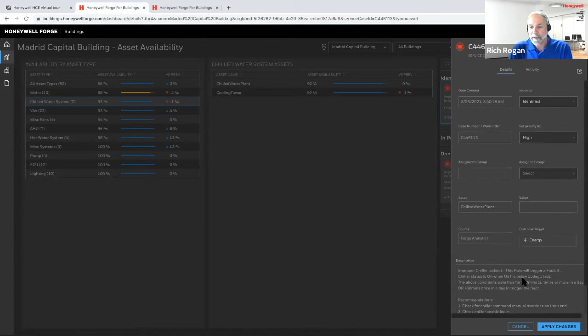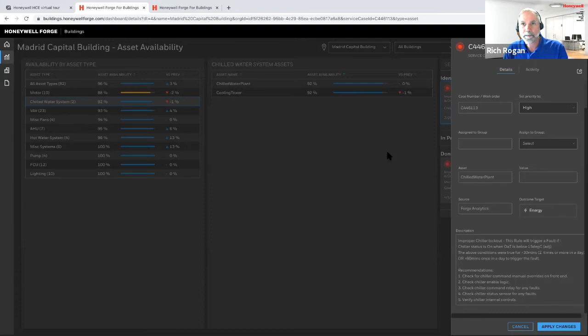Looking at a service case here on the right, you'll see the lightning bolt indicates it likely impacts energy. I'll drill down to see it. A service case is not just the identification that a problem exists, it goes beyond that and makes recommendations as to what an operator, engineer, or technician can do to remediate that particular case. Here we see a chiller that looks to have improper lockout, likely running when it's not supposed to be. The recommendation is to check whether somebody has manually overridden it, check at the chiller itself whether it's been enabled, and look for any faults on the relays, the sensors, and the wiring - a little direction beyond just identifying that there's a fault in the space.